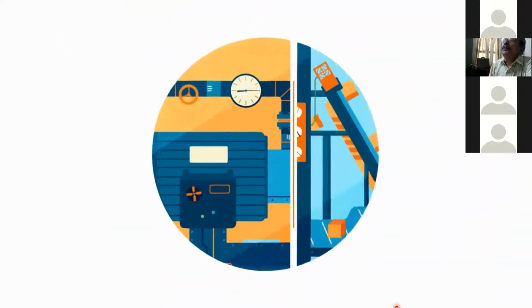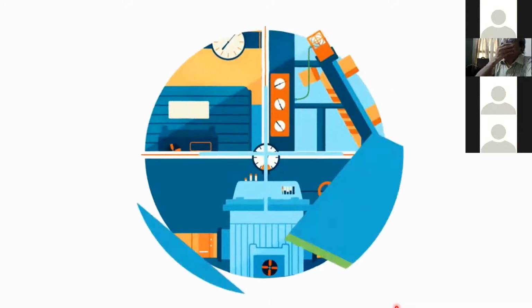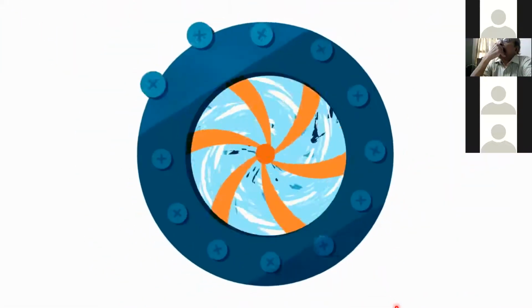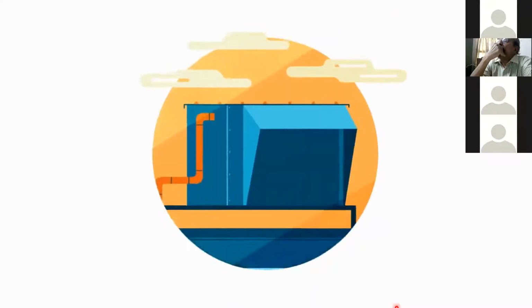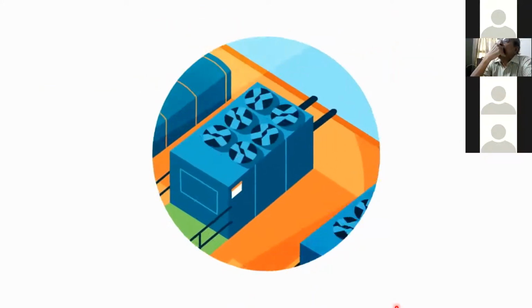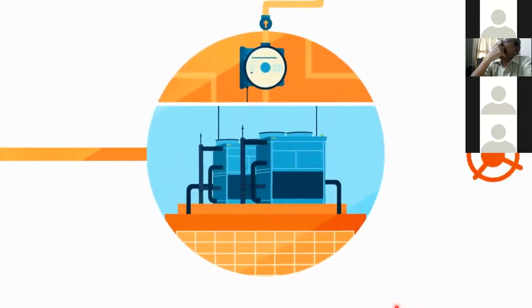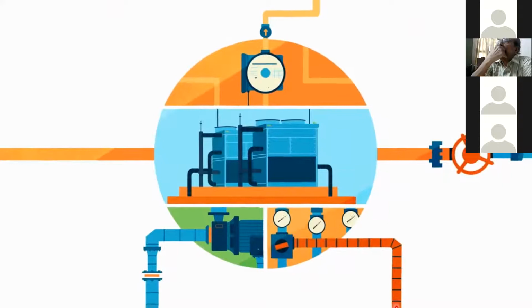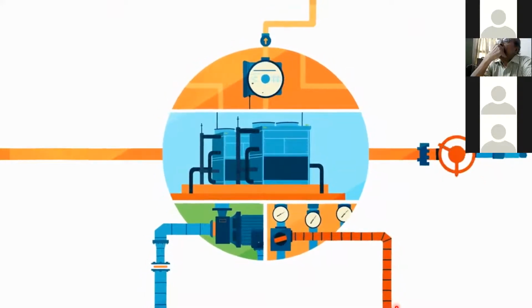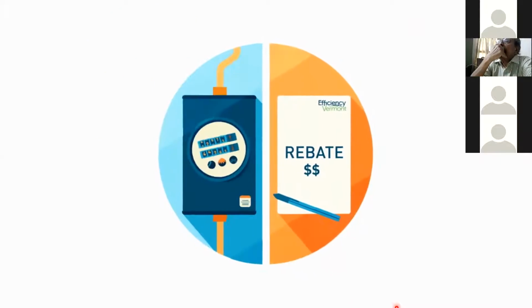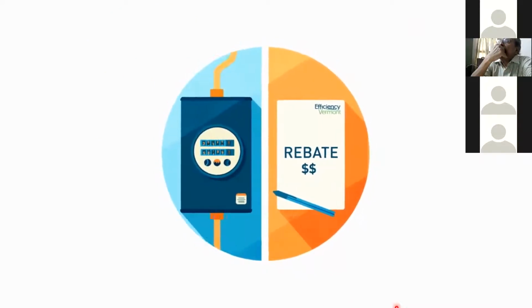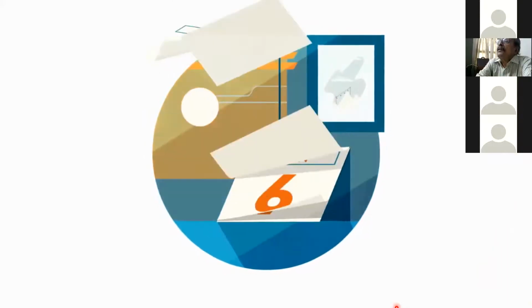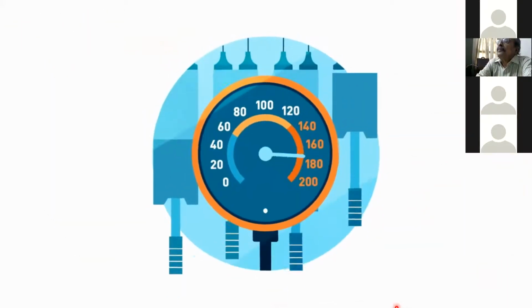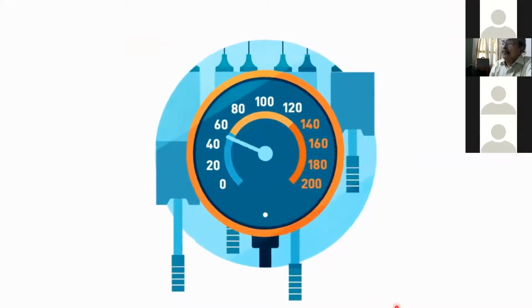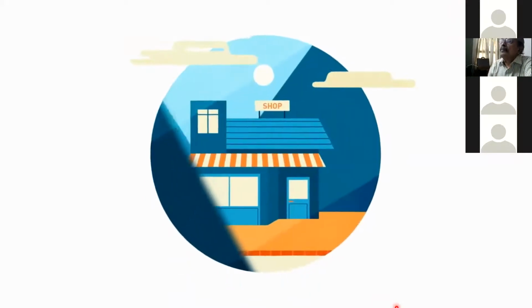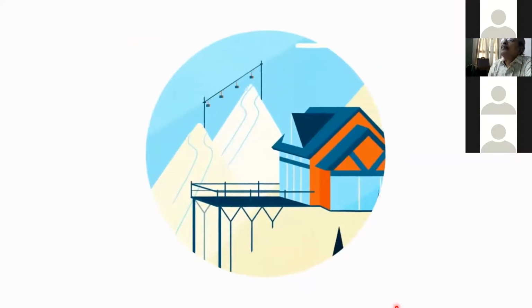There are many places that VFDs can save you energy. Primarily, VFDs are attached to motor-driven fans and pumps. This could include air handlers, exhaust fans, rooftop HVAC units, and more. When it comes to pump systems, hot water pumps, process pumps, and chilled water pumps are common places you may find to be suitable applications for your facilities. Between energy savings and new rebates from Efficiency Vermont, a VFD can pay for itself in less than 2 years, while also extending the life of your equipment and lowering your maintenance costs through less wear and tear. More and more businesses are discovering the power of using VFDs in their workspace.